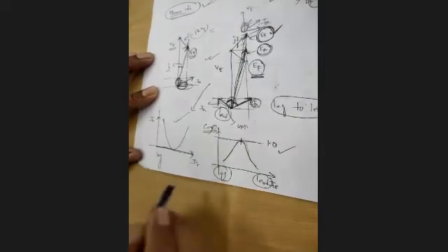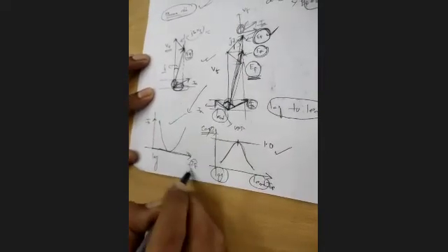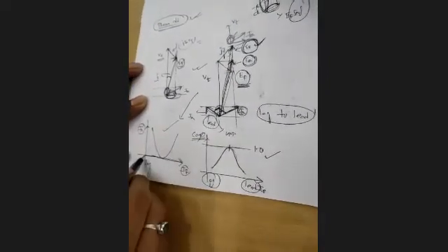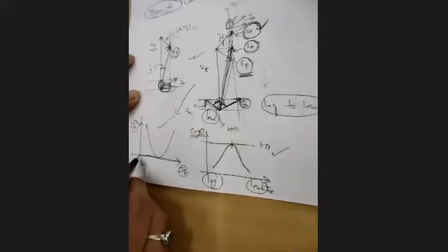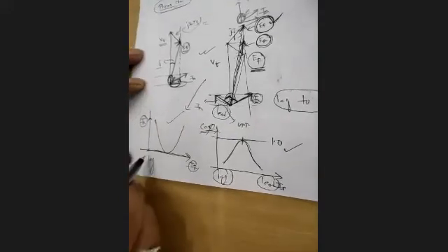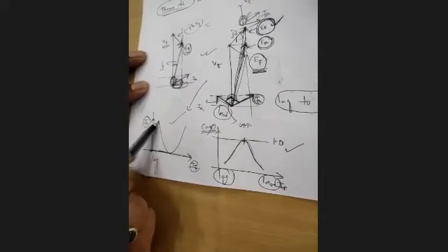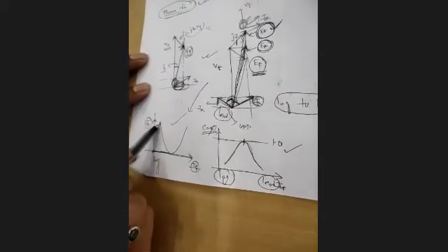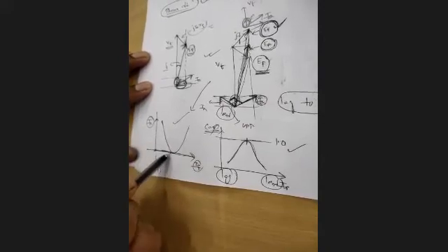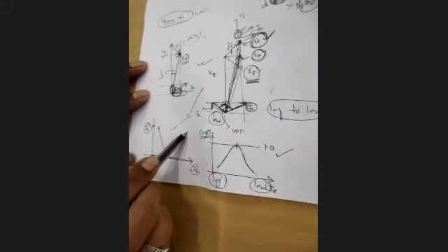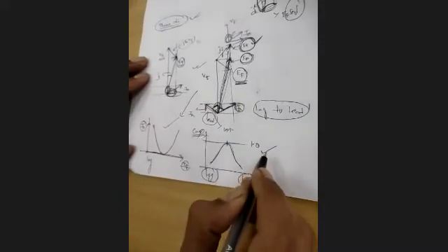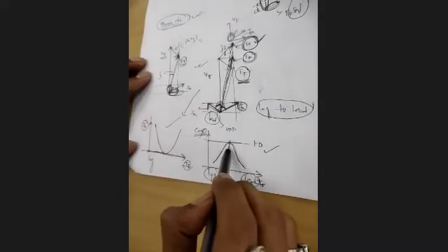Here we will plot If versus Ia. At first we will start the synchronous motor, then we will increase the value of field current. We will see that Ia is initially high, then gets reduced and then increases again. In our next session, the inverted V curve will be plotted.